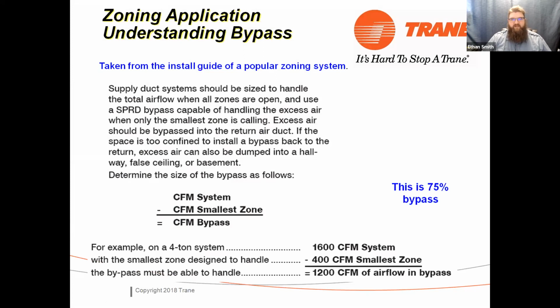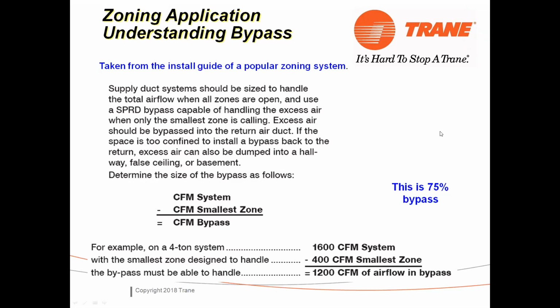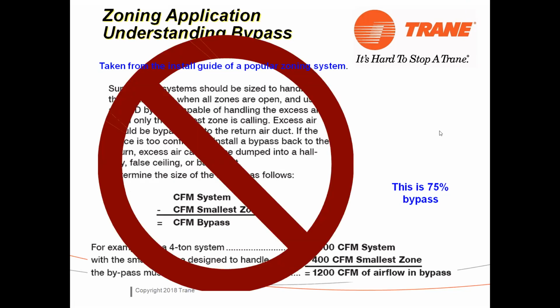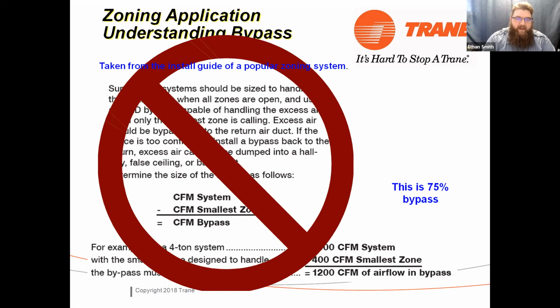This is an OEM zoning system. Okay. Is this good advice? Doesn't look like it. This is terrible advice. Don't listen to this crap. Okay. I have found that if your bypass calculation comes out that you're going to have to bypass more than 30% of your zone, of your capacity, you're going to have problems. That's just my field experience. That's not written anywhere. That's just what I've noticed.